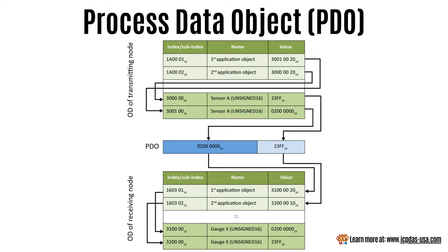PDO, which stands for Process Data Object, is used to transmit real-time operational data between devices in a CANopen network. It is more efficient than SDO for sharing large datasets and is crucial for most CANopen communication. The PDO is often seen as an essential CANopen protocol as it carries the bulk of information, and is used for broadcasting high-priority control and status information in real-time across CANopen nodes.